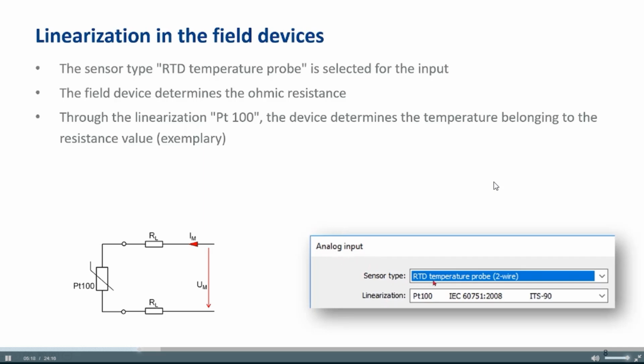You say sensor type RTD temperature probe, and then the device sends a defined current through this loop, and we measure the voltage. According to Ohm's law, the device calculates the ohmic value, and then you say, okay, linearization. If it's a PT100, you define PT100, then the device works with a characteristic and automatically forms the temperature from the measured ohmic value. If you have a PT1000, you say PT1000, but it's not necessary to know what ohmic value you have at 50 centigrade, something like this. It goes automatically.